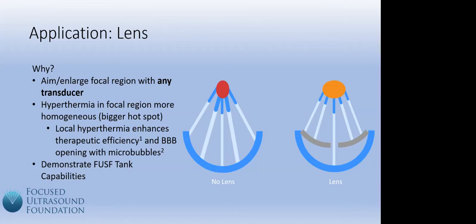For something such as our 350 kilohertz one element transducer, or any transducer really, introducing a lens has the ability to essentially contour your focal region. So that's what we're doing. We're making a bigger hotspot, a region of more homogeneous pressures, because we want, instead of an ablative temperature increase, we want our region to be more of a local hyperthermia. This is, of course, seen in enhancing drug efficacy, as well as in blood-brain barrier opening when paired with microbubbles. And of course, we want to be able to flex a little bit of our Focused Ultrasound Foundation Hydrophone scanning tank by conducting all of our measurements with the lens in our own tank.